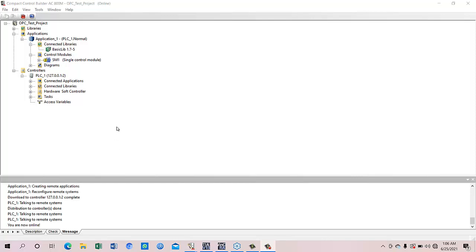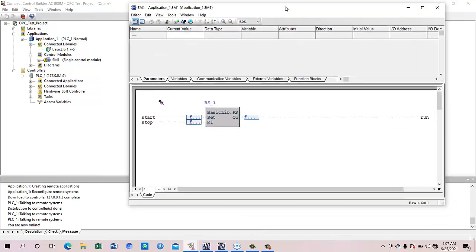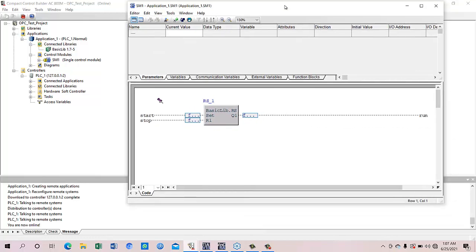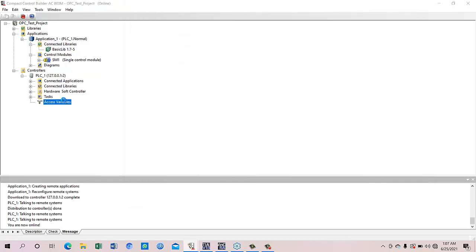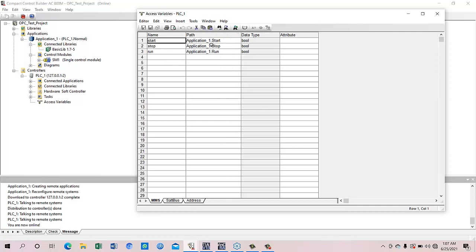This is a typical Compact Control Builder program which is running on soft controller. Here is a one-line program start, stop, and run logic and it has to be sent to the HMI, but we are using third-party HMI so we have the same variable in the access variables pane. So start, stop, and run is mapping in the access variable from application 1.start, application 1.stop, and application 1.run.